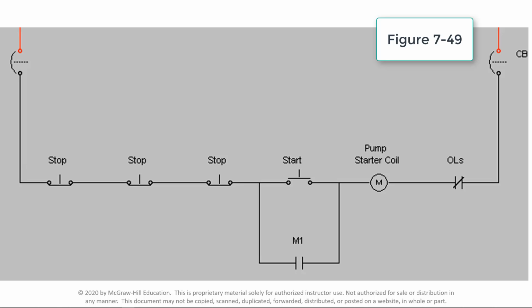For this application, the motor can be started from one location, but can be stopped from 3 locations. The 3 series-connected normally closed stop push buttons provide the NOR function of the circuit. Once the circuit is energized, if any one of the 3 stop push buttons is pressed, the starter coil M will de-energize.